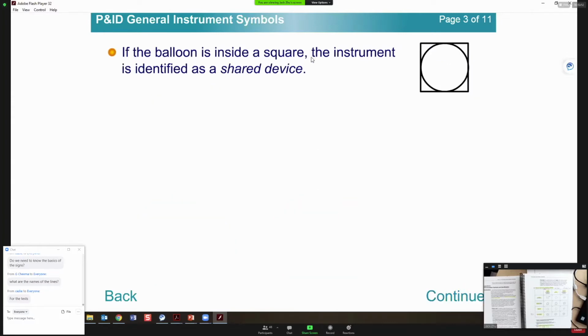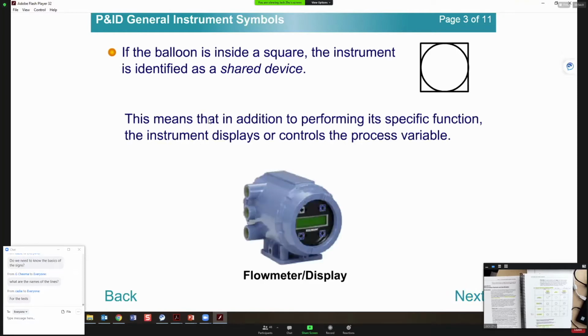If the balloon is inside a square, that will be a shared device. So you want to ask me, what's a shared device? This means that this sensor is not only going to measure something, but it also has a display or controls. So you can see down here, this one is a flow meter. It will sense how much liquid or gas is flowing through the pipe, but you also have a display on here. It will show the flow rate of this measurement.